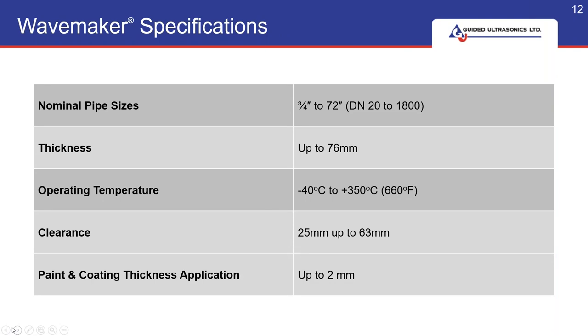We've got many options of rings in various sizes. You can typically go from three-quarter inch — which we have a claw for — for tubes and pipes, up to 70 inches with the AC and compact rings. You also have the option to combine two rings together, and our temperature range goes from minus 40°C up to 350°C using the high temperature rings.